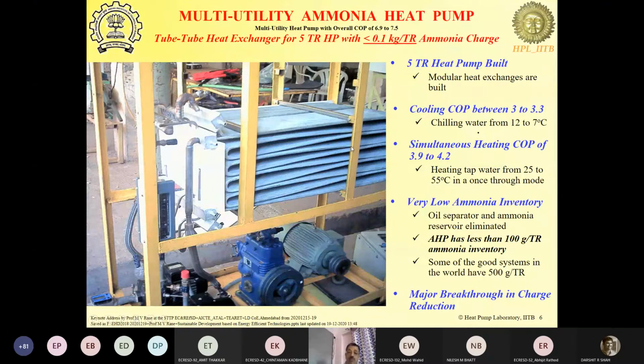Even with the latest systems, even larger ammonia systems, it is quite challenging to get the charge down to less than 0.1 kg per ton, which we achieved more than 10 years ago. Reducing the charge in the system is very useful because it reduces the hazards if the refrigerant is toxic or flammable, like ammonia. And if the refrigerant has zero ozone depleting potential and zero global warming potential, then reducing the charge also makes the system more sustainable.